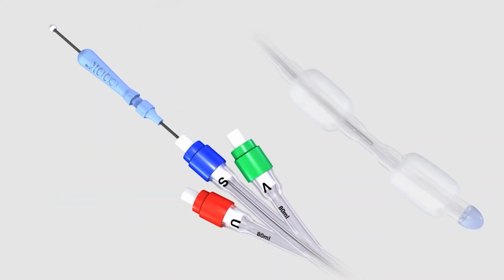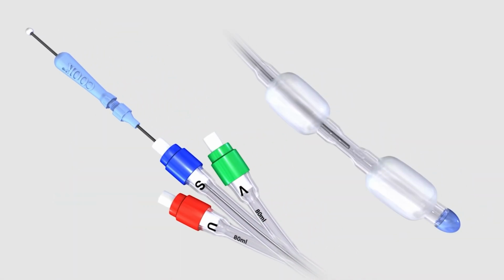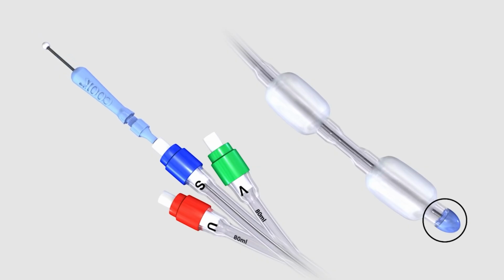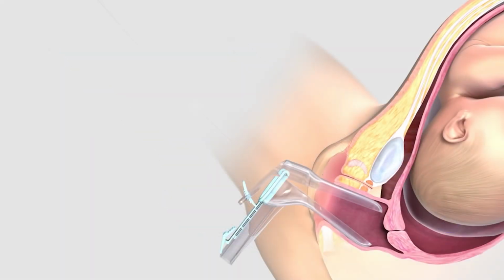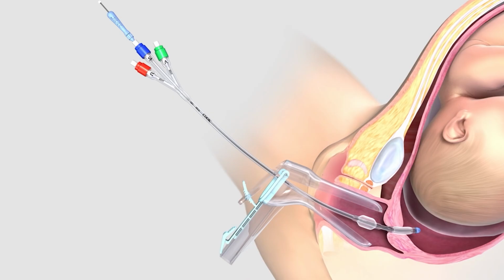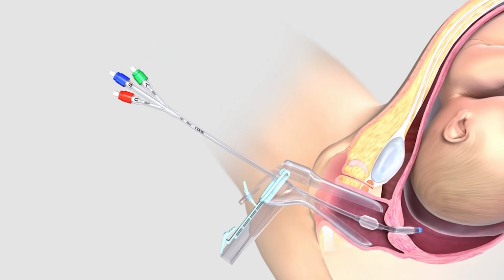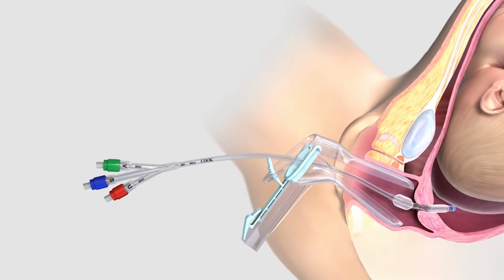Loosen the fitting on the proximal hub of the stylet and adjust the wire so that the distal tip of the stylet is even with the distal tip of the cervical ripening balloon. Tighten the fitting so that the wire does not move during manipulation, and seat the adjustable handle firmly into the blue port labeled S. If necessary, use the cervical ripening balloon with stylet to traverse the cervix. When you have traversed the cervix and the uterine balloon is above the level of the internal os, remove the stylet before you advance the catheter any further.